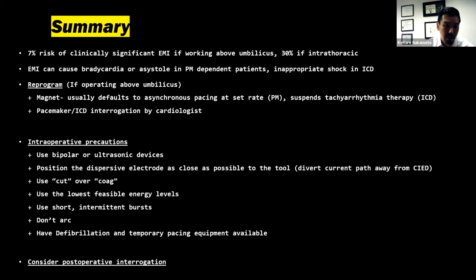Intraoperatively, you need to follow these precautions. Try to use bipolar or ultrasonic devices as much as possible. Position the dispersive electrode as close as possible to the active electrode or the tool. Divert the current path away from the CIED. Use cut over coag as much as possible. Use the lowest feasible energy levels and use short intermittent bursts. Also, don't arc. Always have a defibrillator and temporary pacing equipment available. And don't forget to consider post-operative interrogation of the CIED. That's it. Thank you.